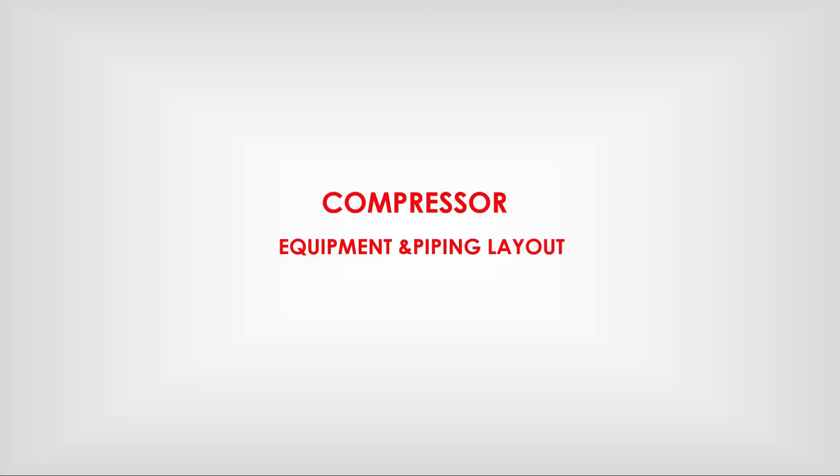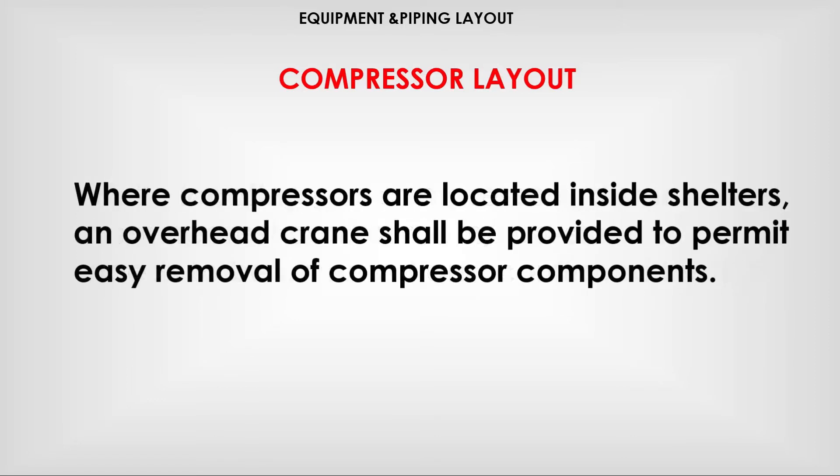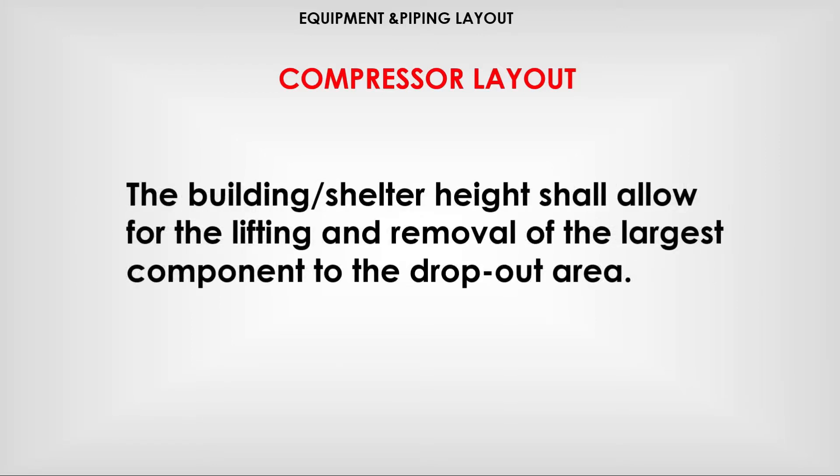Equipment and piping layout for compressors: while locating a gas compressor, the distance from the nearest control room substation needs to be checked and confirmed by HSE. Where compressors are located inside shelters, overhead cranes shall be provided to permit easy removal of compressor components. The building and shelter height shall allow for the lifting and removal of the largest component to the dropout area.